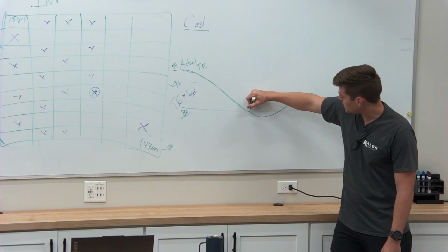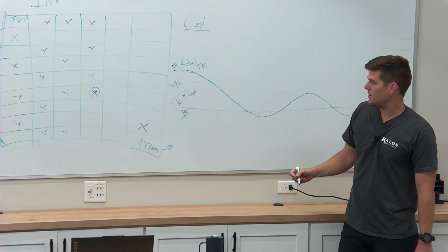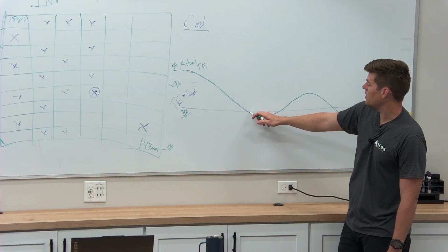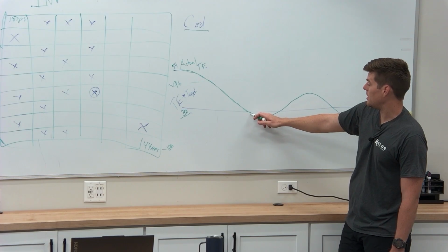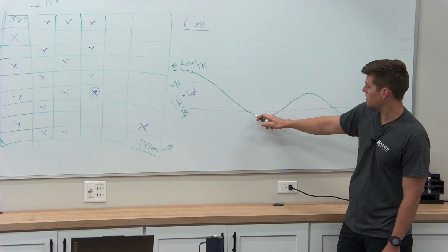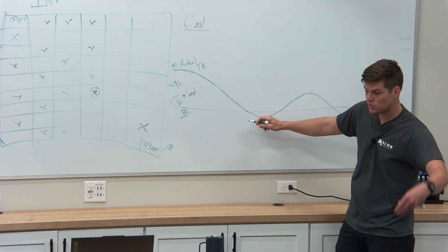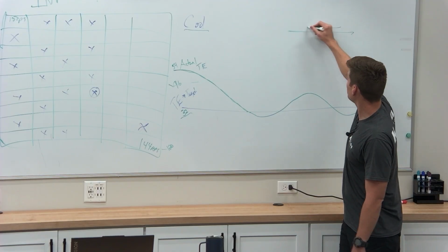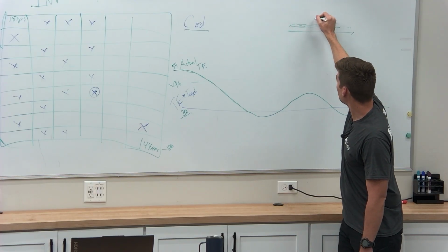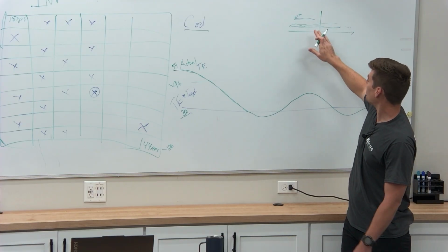And so what happens when it hits this point here? It says, finally, I've made it. And let's say it landed here. And it says, okay, I'm here, I'm running. Okay, and it stays at that speed. But then let's say one of the indoor units turns off because it satisfied temperature. So you get a close, right? When it closes, you get a line right here, and refrigerant is just flowing by, going in this direction, and then it just completely shuts. And what happens to all that refrigerant?